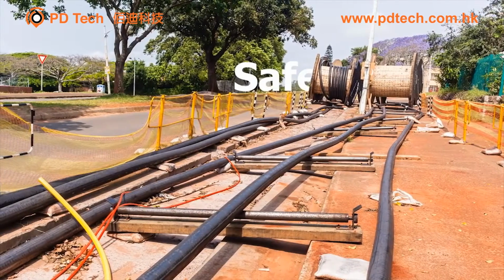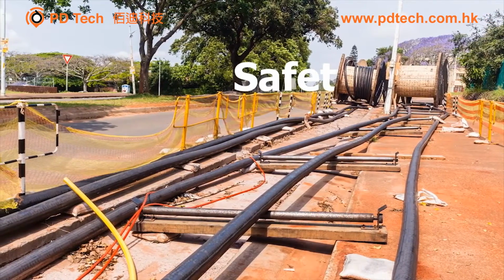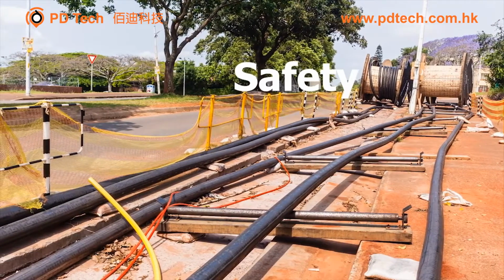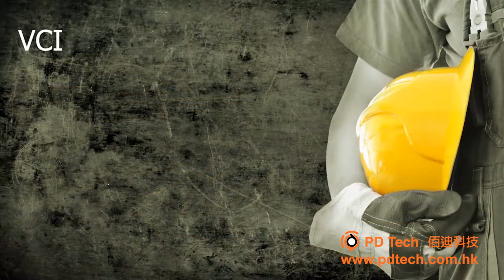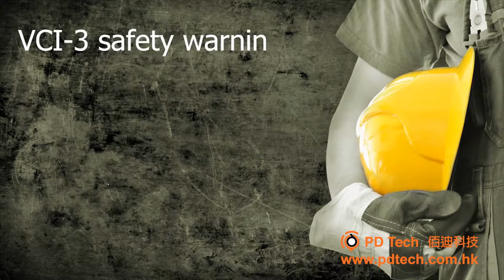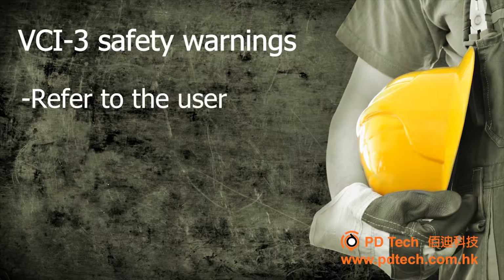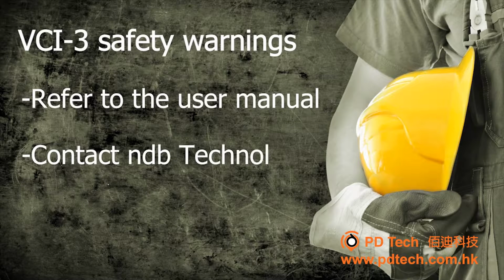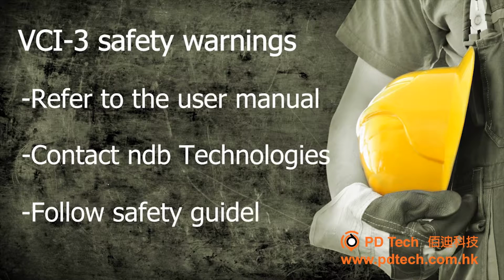Safety is second to none, and with the VCI's dual ground test method, workers are assured of the highest protection level. This video describes how to safely operate the VCI-3 for easy and accurate cable and phase identification. Always refer to the user manual for detailed information and safety warning. Contact NDB Technologies Technical Support Department if you have any doubts or questions on the operation of your equipment. Follow your company's safety guidelines and avoid dangerous electric shocks. Safety is the operator's responsibility.